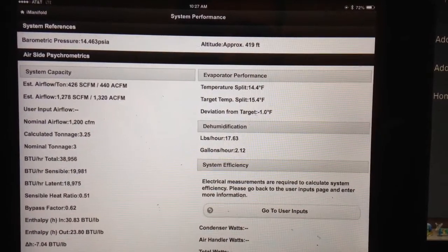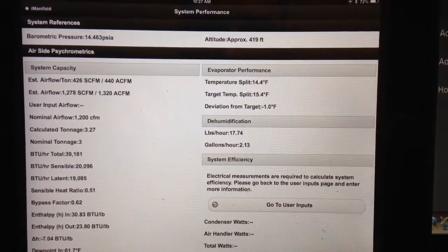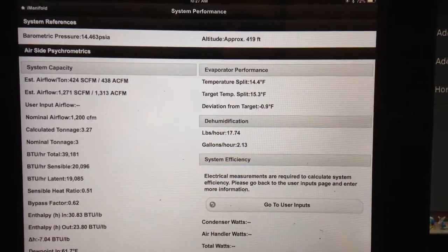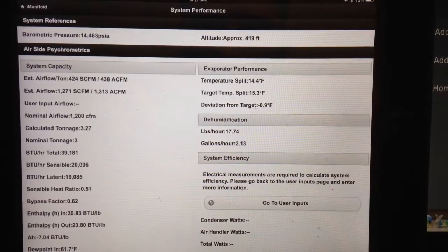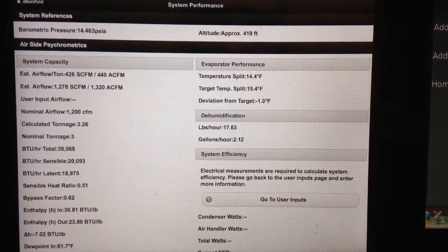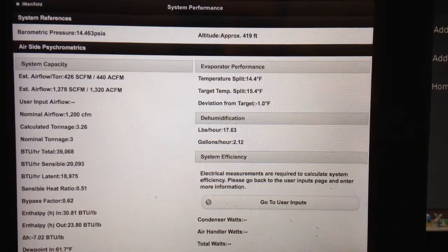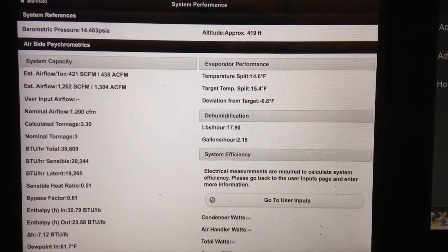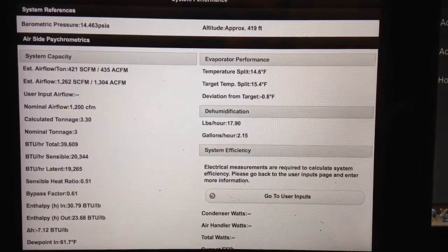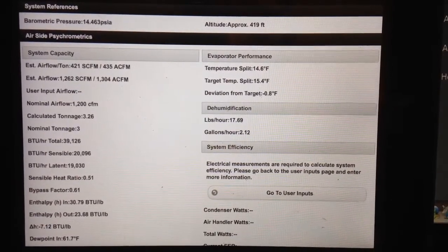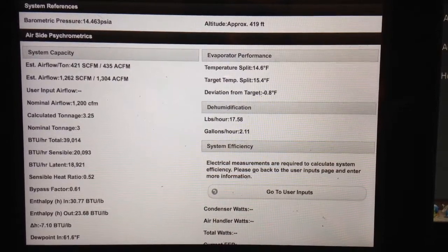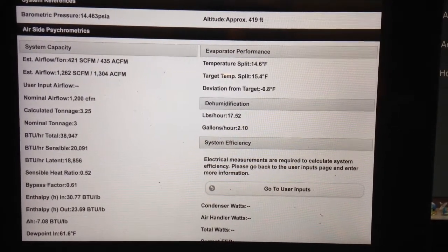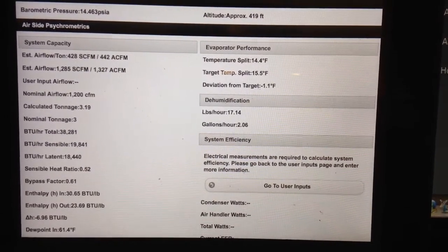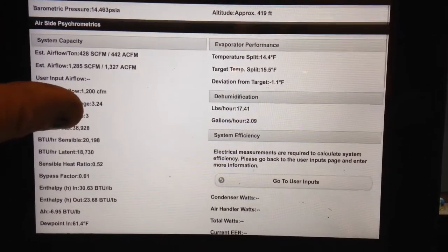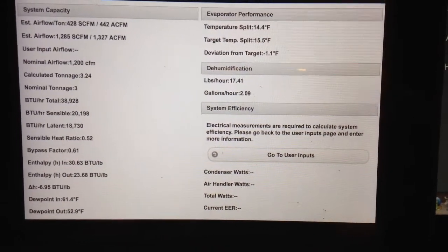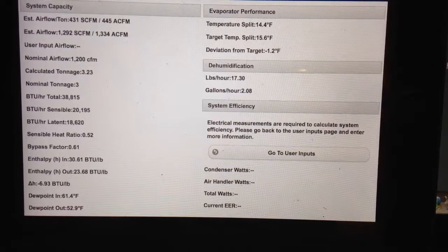Currently, under the coil performance that I'm getting, I've got a standard CFM of 424 per ton and 1271 overall. My target temperature split is short by 1 degree. My calculated tonnage is 3.3. I've got 39,000 BTUs total, with 20,000 allocated to sensible and almost 19,000 allocated to latent, with a sensible heat ratio of 0.52, and I've got a bypass factor on my coil of 0.61. Dew point entering is 61.4 and dew point exiting is 52.9.